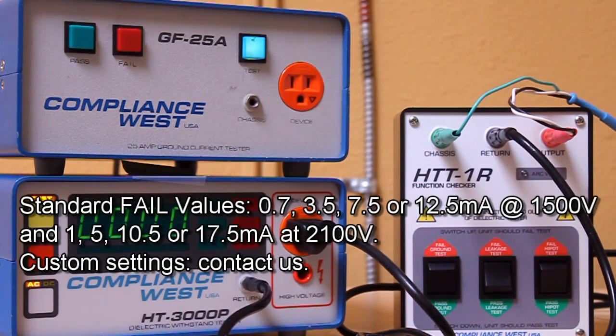We offer failing leakage current levels of 0.7, 3.5, 7.5, and 12.5 milliamps at 1500 volts AC or DC, and failing current levels of 1, 5, 10.5, and 17.5 milliamps at 2100 volts AC or DC. If different values are needed for your installation, we can provide them.